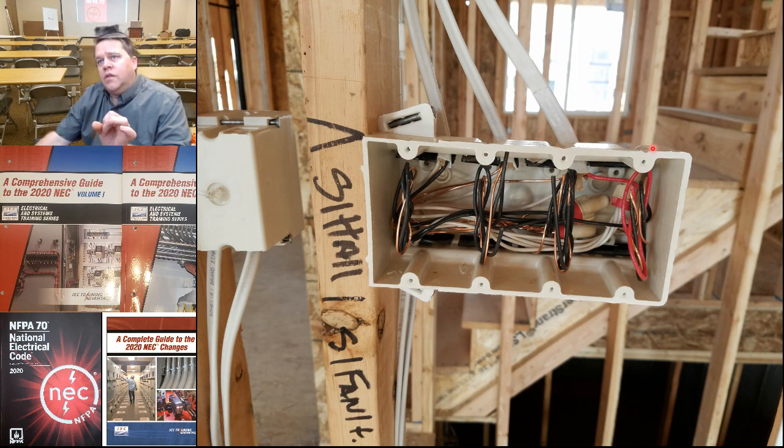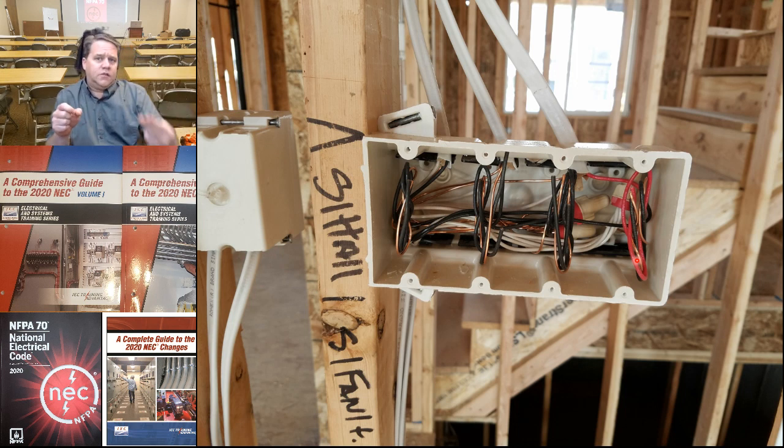The reason I wanted to show this is specifically this 4th switch here, which is a 3-way. If you look at Table 310.15(C)(1), one of the things you'll notice at the bottom of the table is it says that if the ungrounded conductors are connected in a way that you have multiple ungrounded conductors but only one would be energized, then we only need to count 1. So in a 3-way switch, we come down with the hot, we've got 2 travelers, and then we leave with a switch leg. No matter what position you put either of those switches in, one of the travelers is always on, the other is always off. So we don't need to count both travelers, right? Because there's no way that you could have them both on simultaneously.